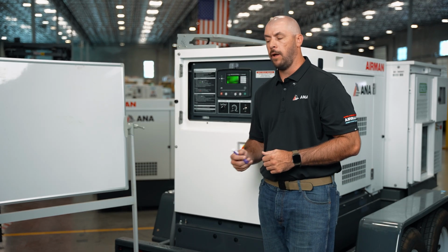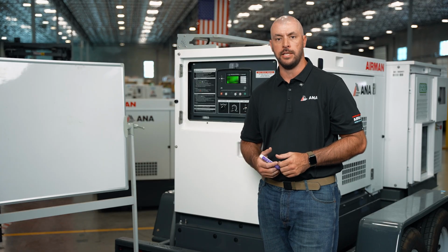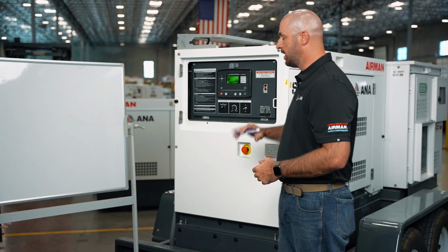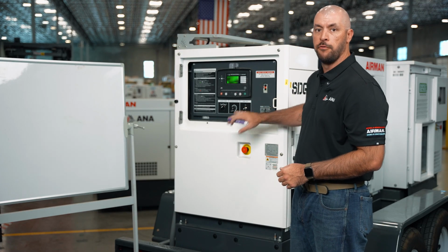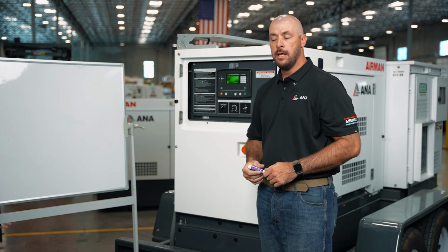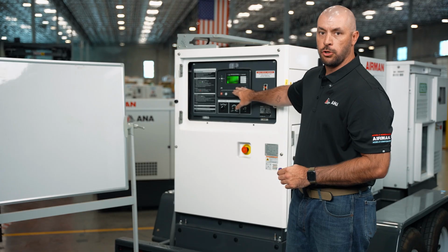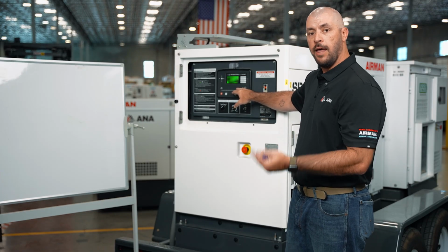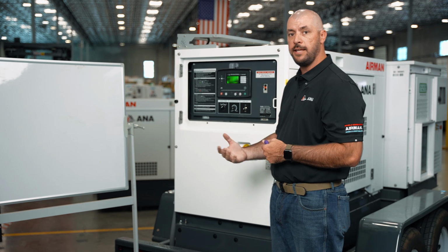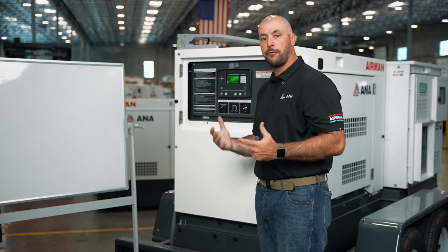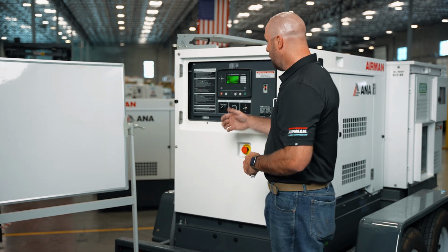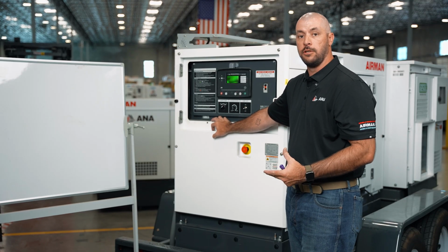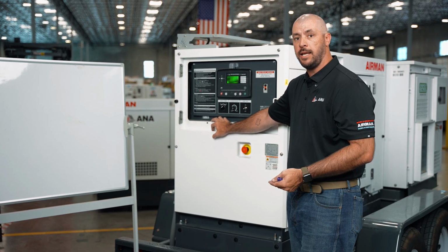Today we want to talk about a common topic we have during our training sessions with customers and what they seem to find a lot of value in. What this is, is determining the average amount of load that your generator has on it. Now, through the features of the Deep Sea Controller, we're able to capture the total amount of load that your generator has had on it, and then we can take your engine hours and divide those numbers and come up with the average load that your generator is running. This is extremely important, and it helps you determine what age your generator is at and what kind of maintenance may need to be done.